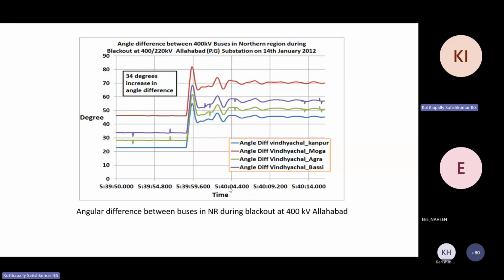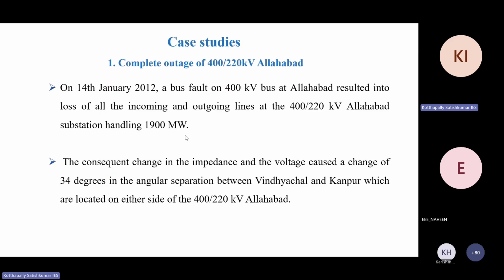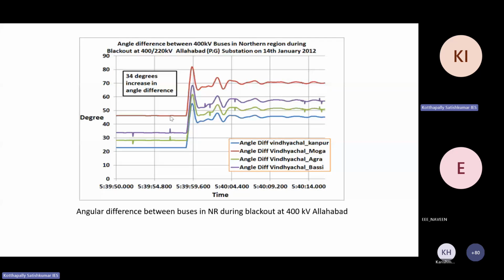So you can see the accuracy of the data. Using this data, once the fault occurred at around 5:39:56 and 55 seconds, all three phase voltages shifted by around 34 degrees. So all three phase voltages are moving. So it's simply a three-phase fault.